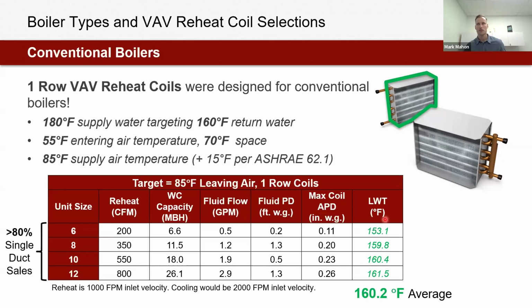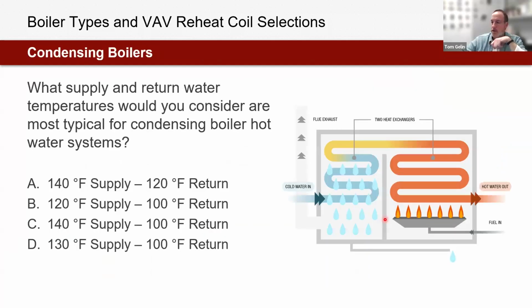That could fall outside of that 20% limit in some cases, though, and that would be a good consideration to assess. Maybe that'll be your next control strategy, is electric reheat for lower airflows on electric heat, but maybe in a year or two. We have some irons in the fire on that too. I think there may be more 26 release options, but plenty in the works internally on our end, things to optimize for electric reheat as well. Yeah, thanks, Jonathan.